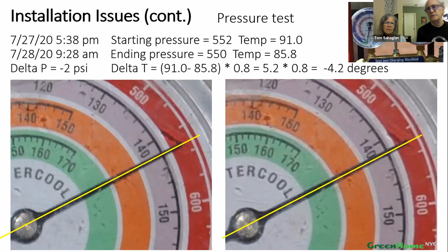If the outdoor temperature where you're doing the test changes, the pressure can drop slightly. You can see here it looks like it's about 560, 555, and here it's much closer to 550. You might say the pressure dropped, so there's a leak. Not necessarily, because if the temperature has dropped even more than that, then actually you're okay. It's a subtle thing, but you have to focus on it, because otherwise you could easily make a mistake.